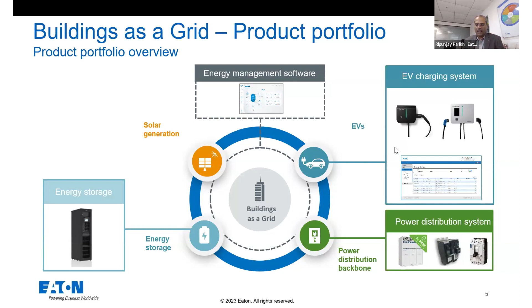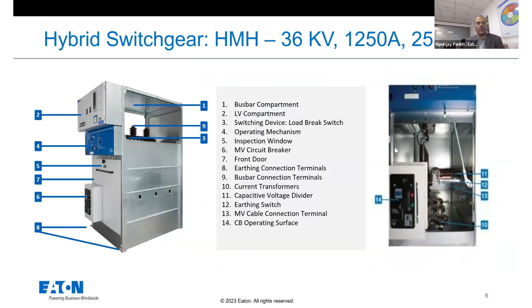One of the biggest challenges today is bringing better operability for switchgear. In the 33 kV space, I want to talk about something called hybrid switchgear, where we reduce the footprint to more than half compared to conventional air insulated switchgear, while bringing a lot of user operability at the site level through modularity, unlike a conventional RMU where you cannot do anything. The concept is a fixed breaker, isolator and earth switch, completely built up in a compact, type-tested space.